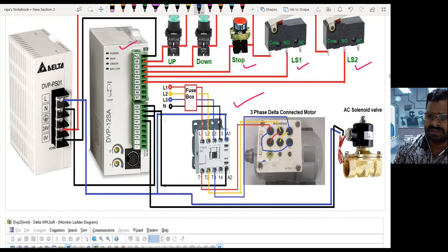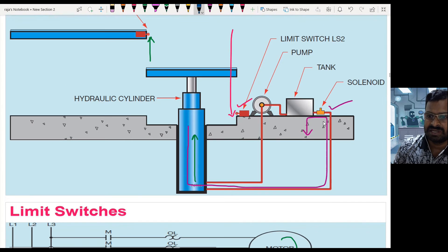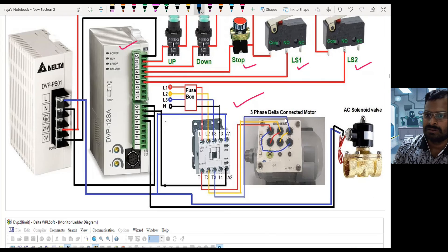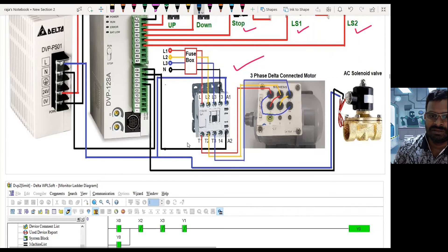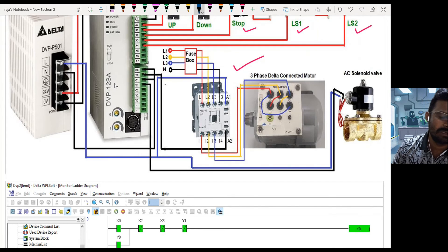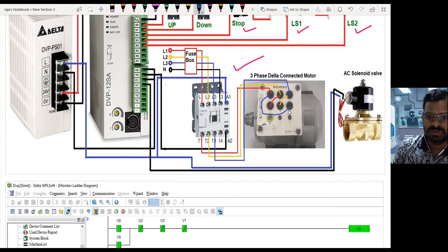When the solenoid is energized, due to the weight of the cylinder piston, the piston comes down and liquid flows through the solenoid to the tank. The solenoid is directly connected from the PLC output module, which is also in sinking configuration, so these two output elements act as sourcing elements.